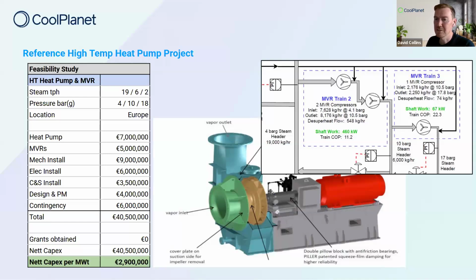This gets into another level of CAPEX. The budget here was over 40 million for this project, producing up to 19 tons of low pressure steam and 2 tons of high pressure steam at over 18 bar. The CAPEX here is at another level compared to previous projects, nearly 3 million per megawatt installed. This is the direction companies are having to look at now for a decarbonization strategy, because you'll only get so far with low temperature heat pumps—you need to combine that with mechanical vapor recompression.